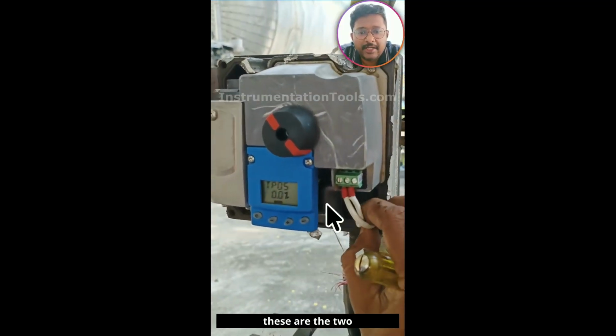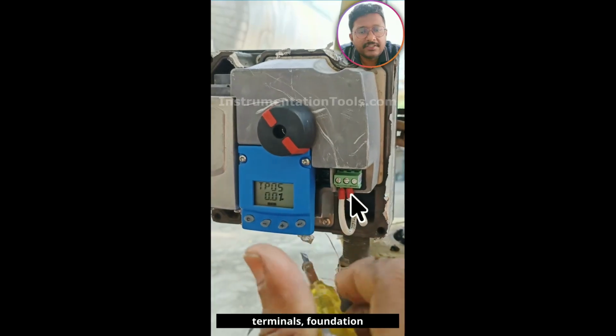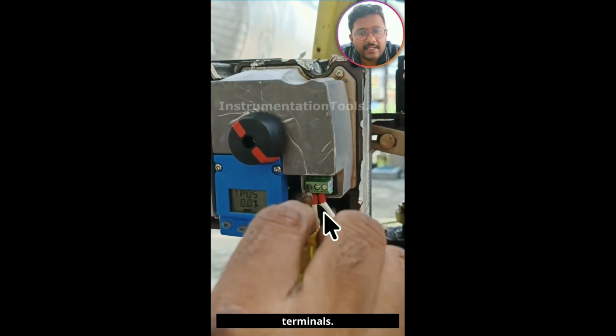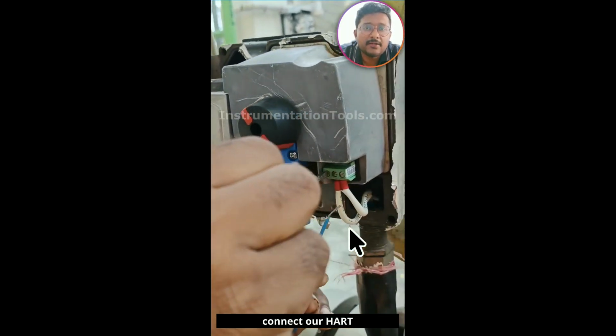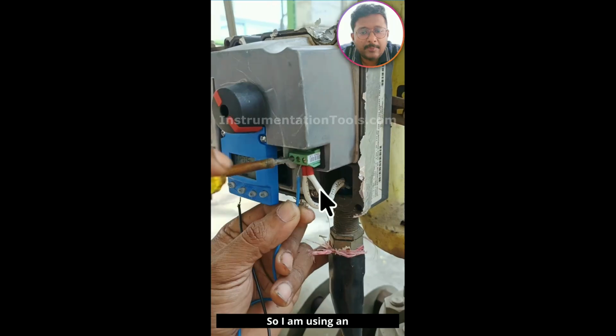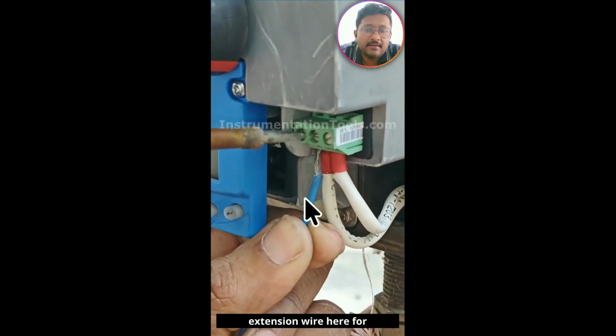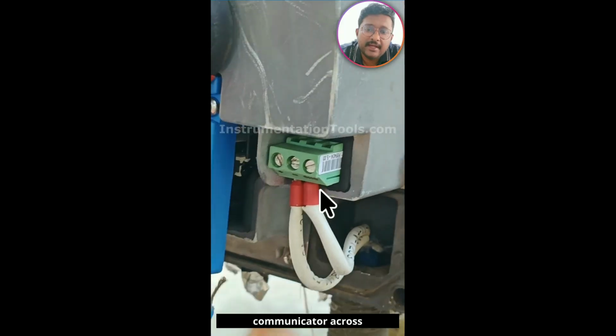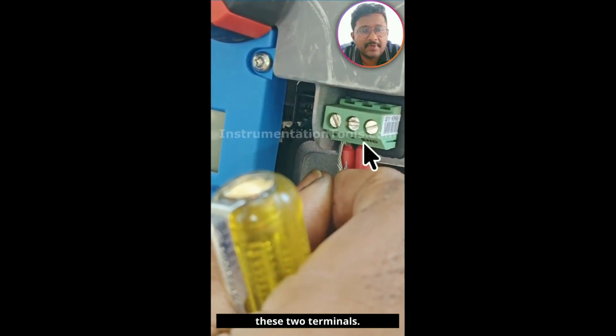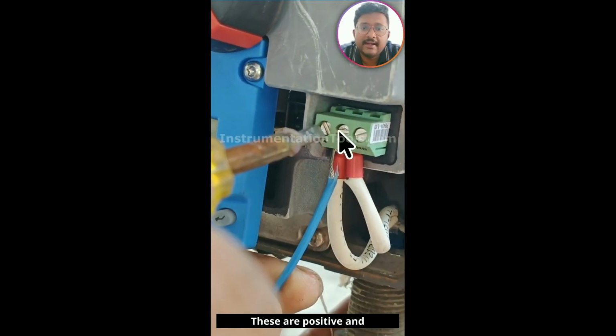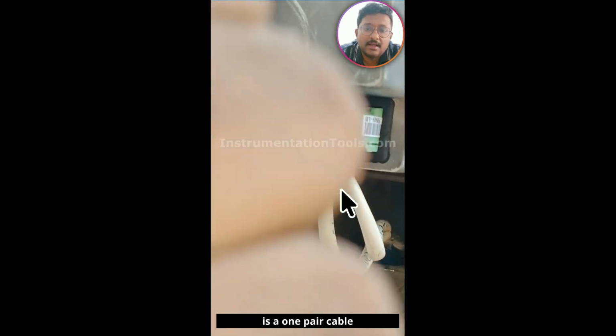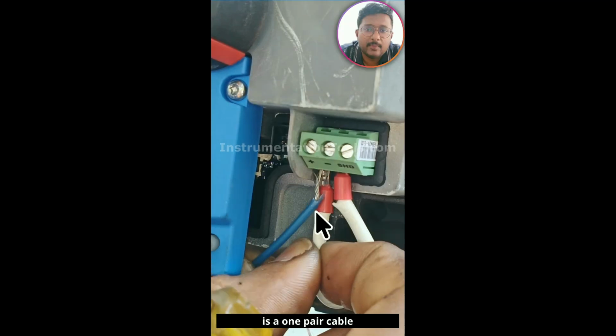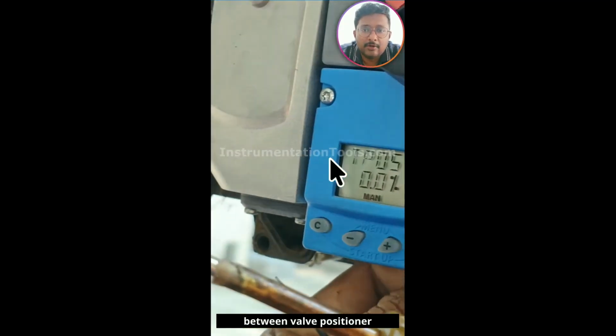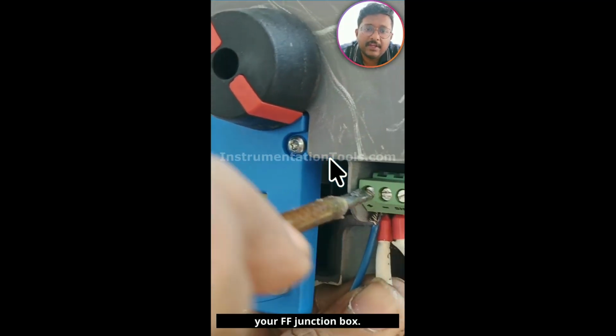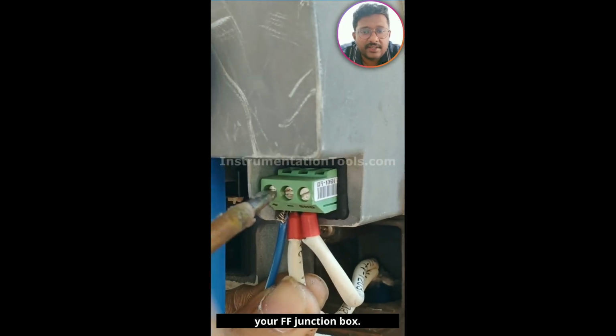And these are the 2 terminals, the foundation fieldbus cable terminals. Across these 2 terminals, we have to connect our HART communicator. So I'm using an extension wire here for connecting the HART communicator across these 2 terminals. These are positive and negative terminals. It is a 1 pair cable between the valve positioner and your FF junction box.